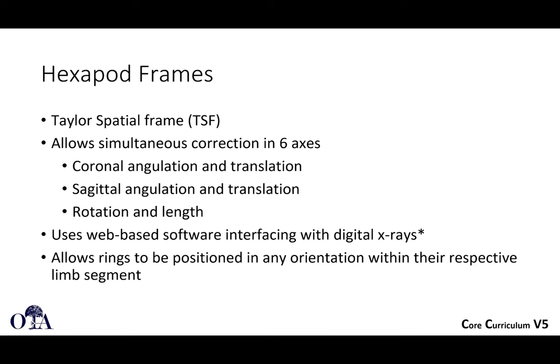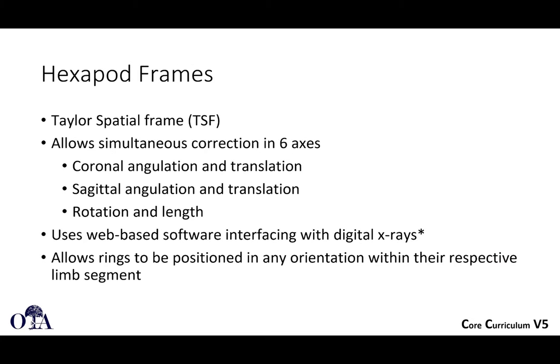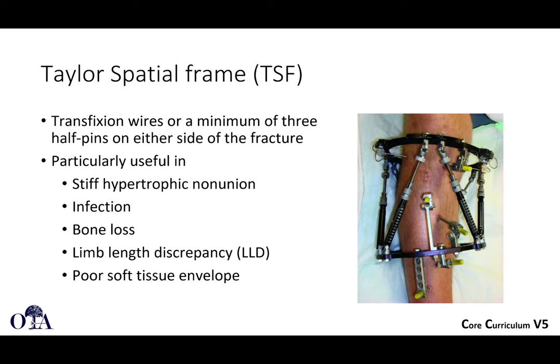A hexapod frame — an example of this is the Taylor Spatial Frame, which looks like this. It allows for simultaneous correction in six axes: coronal angulation and translation, sagittal angulation and translation, and rotation and length. It uses web-based software interfacing with digital x-rays to determine what needs to be done with each telescoping rod to achieve the desired alignment. The rings can be positioned in any orientation within their respective limb segment, and within the degrees of freedom each telescoping rod allows, it can use any reasonable starting point to achieve correction.